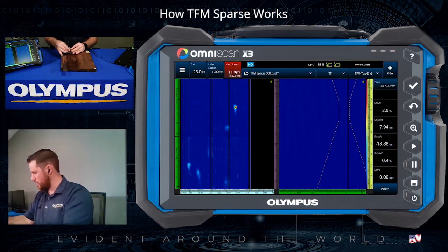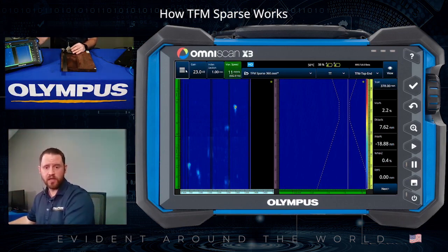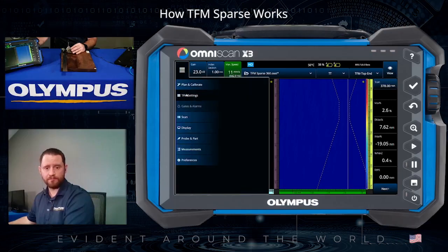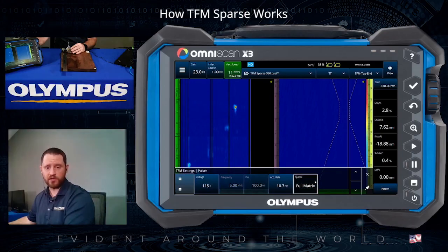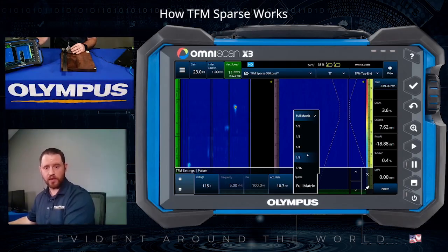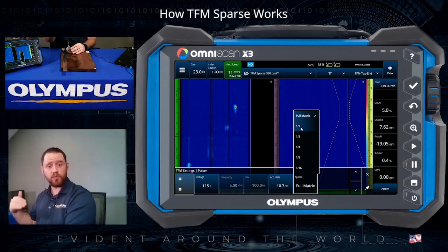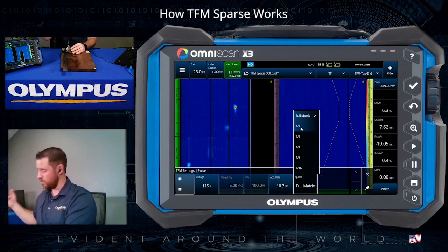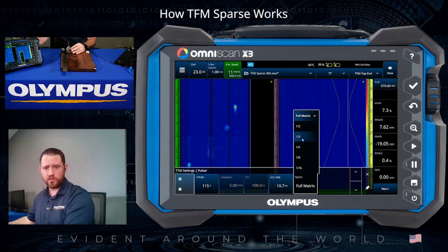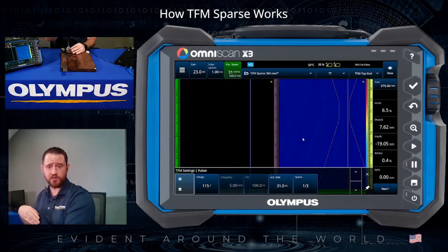So what we'll do now is activate the sparse setting and compare and contrast what that looks like. In our TFM settings, under our pulser configuration is where we find our sparse mode. Obviously right now it's running full matrix, but we do have the flexibility to apply different levels of sparse firing: 1x2, 1x3, 1x4, 8, and 16. And again, going back to what we talked about earlier, this will skip whatever number of elements that you see in the selection here. So if we have this set to say 1x3, this means it'll skip 2 elements and fire every third element of the transducer.